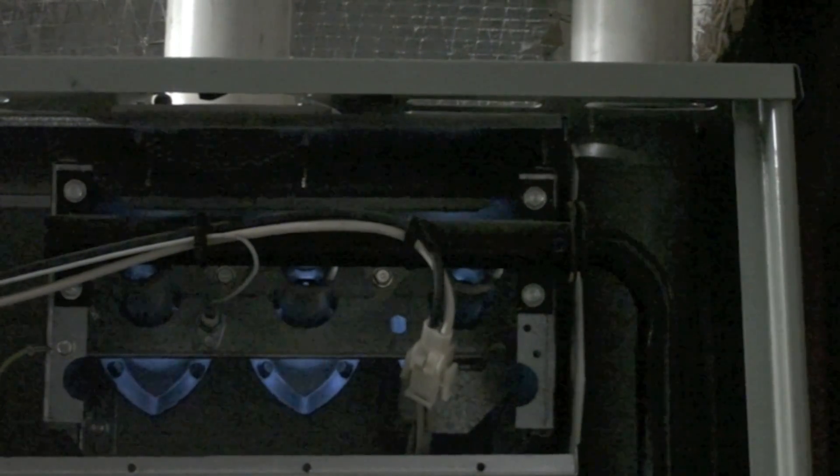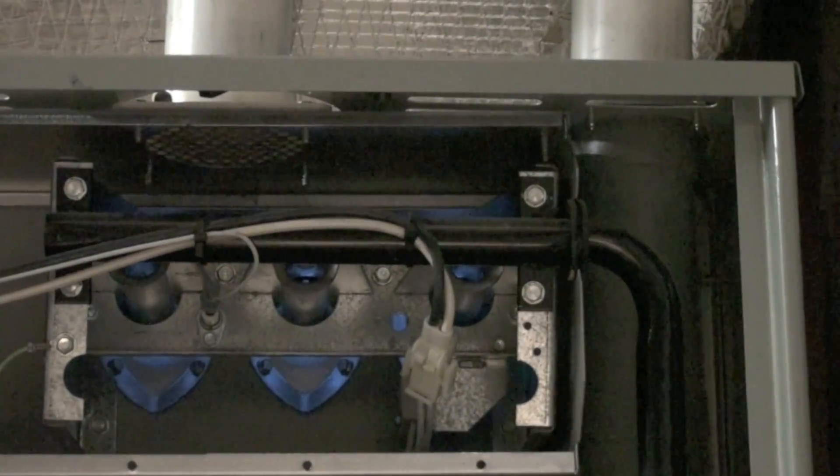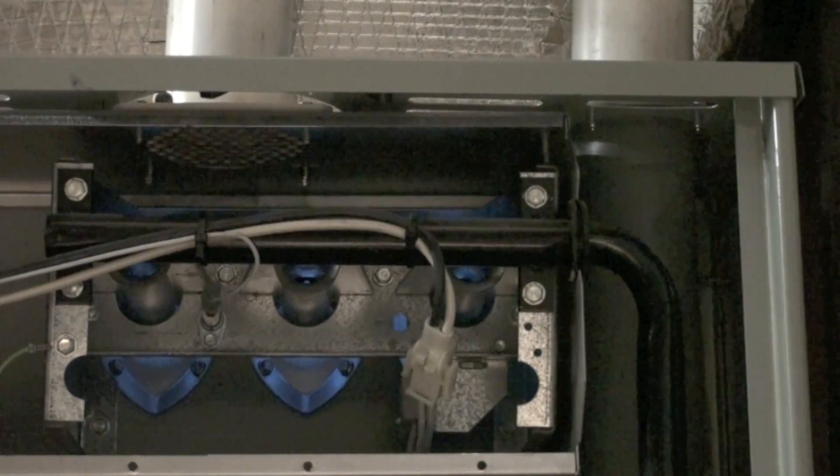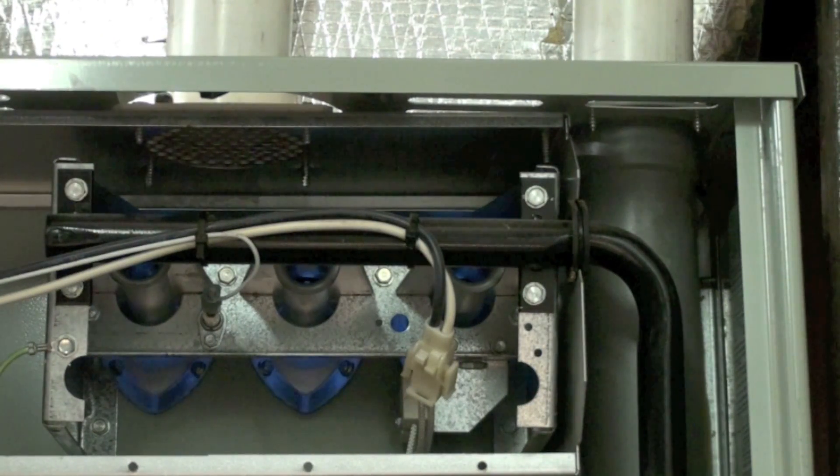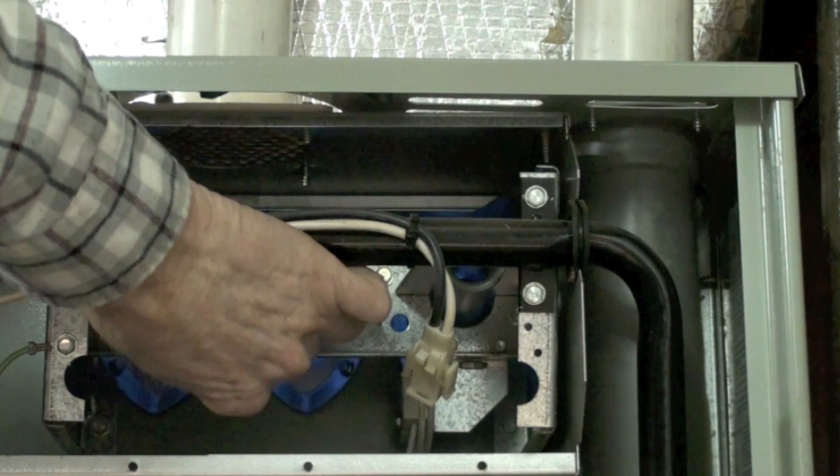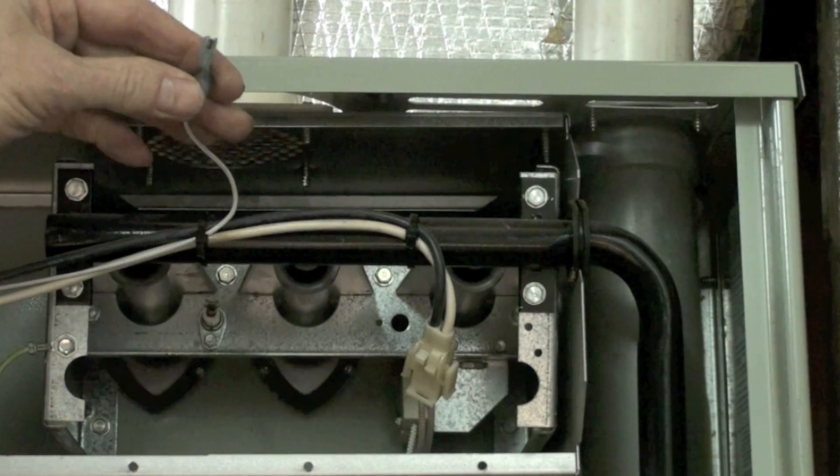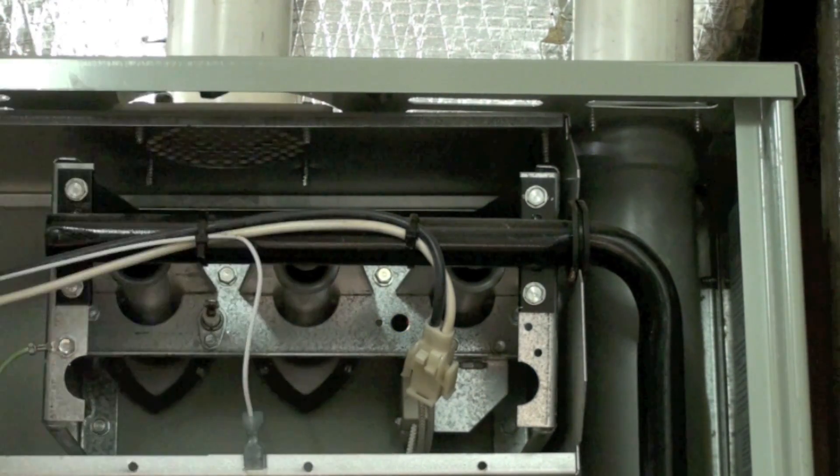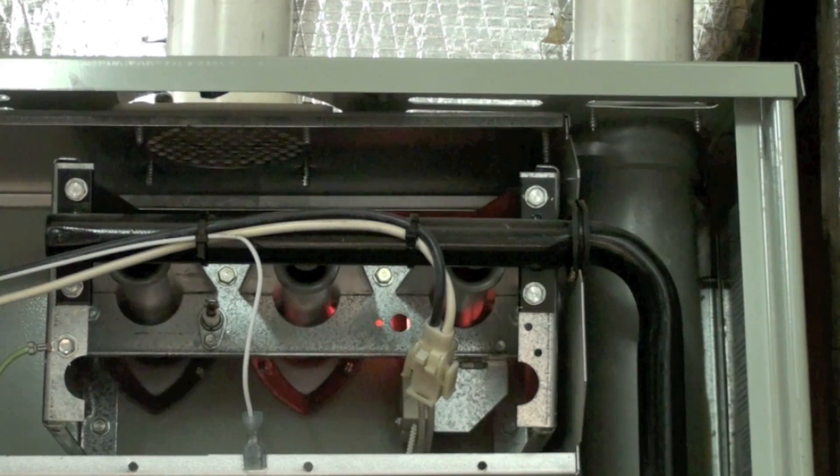Let's get a little closer here and we'll get some light back. Okay, the burners are operating and I'm going to induce a failure. I'm going to remove the wire from the flame rod.